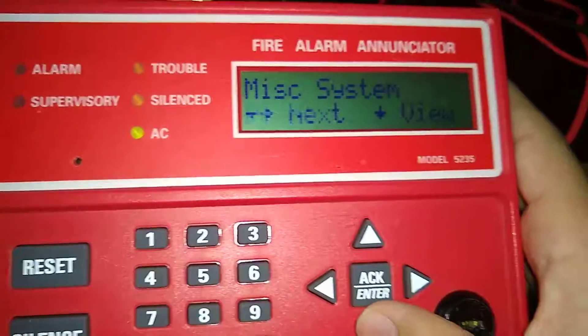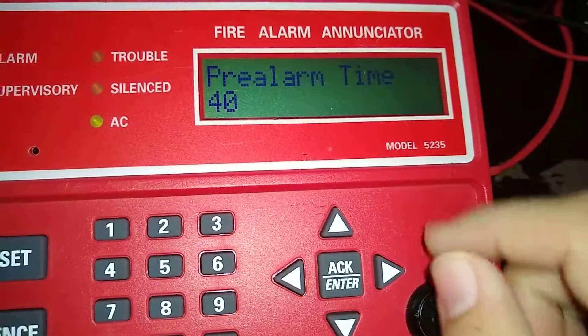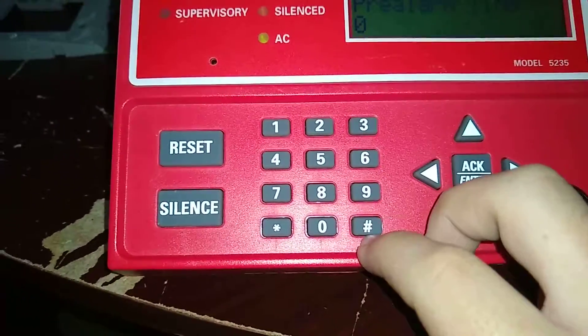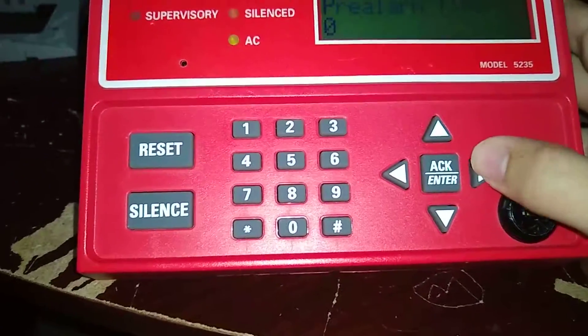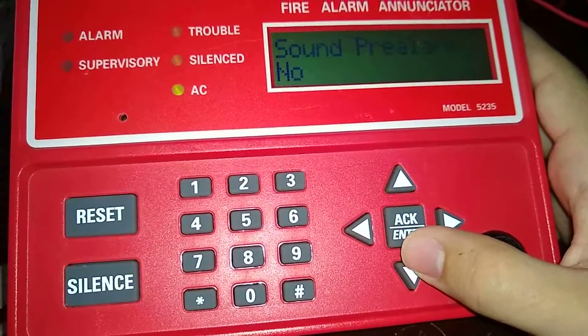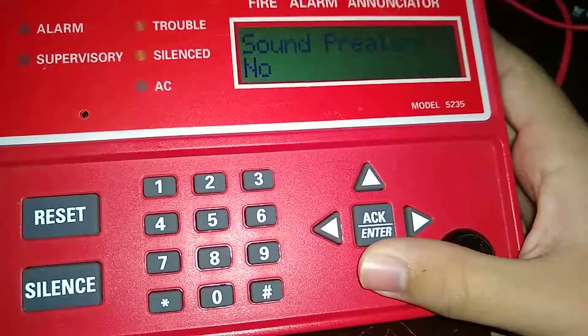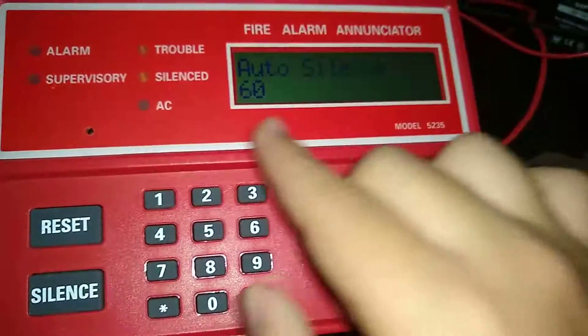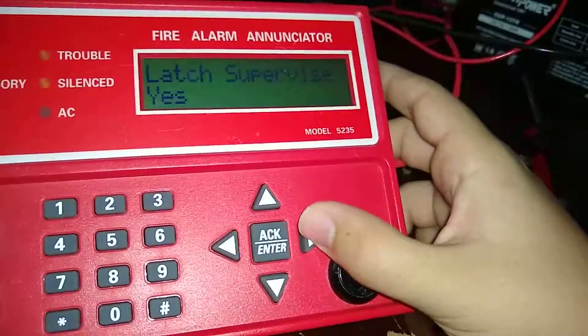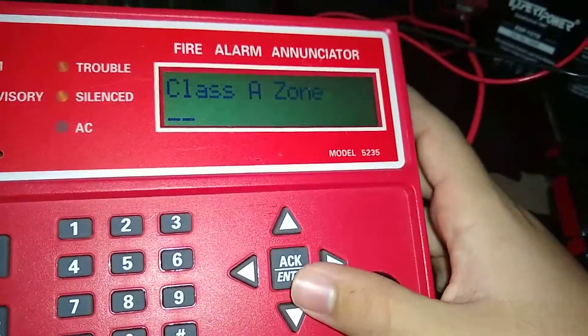Now misc system. Pre-alarm time — how much time do you want for pre-alarm? I don't want any pre-alarm so I have it set to zero; you can also clear it by pressing pound. Sound pre-alarm: I have mine set to no. Auto silence after sixty seconds: no auto silence. Latch supervisories: you can do yes or no — I have it set to yes. Class A zones — any class A zones one through ten.